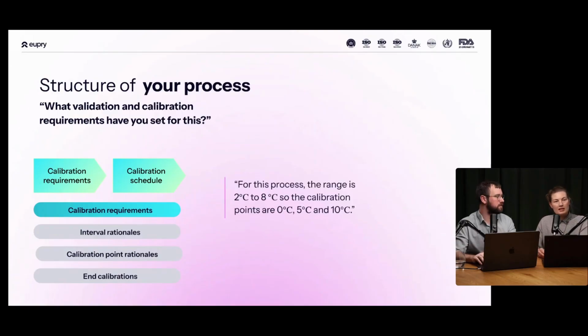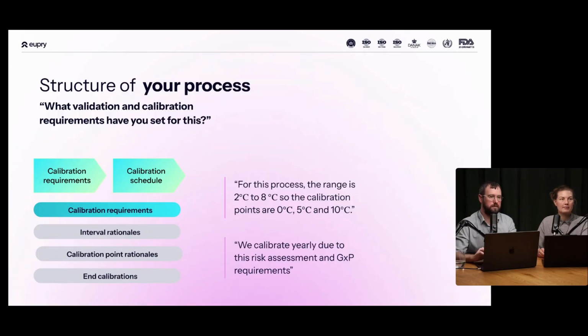So this is an answer you could give if you were audited: for this process, the range is 2 to 8 degrees, as we had before, and therefore we chose these calibration points - 0, 5, and 10. Why are these the calibration points? Because they cover below the actual range and above the actual range. So this would be a clear and good choice of calibration points for this one.